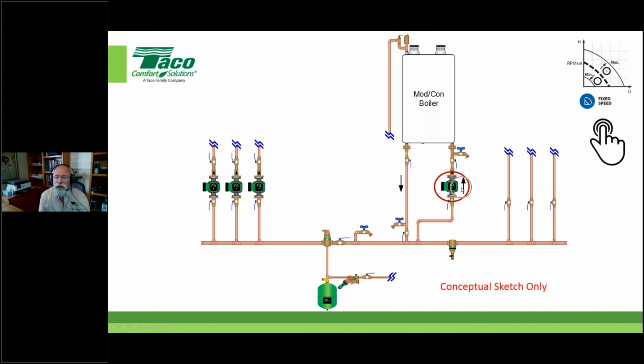So the reason—notice no more control wire—it's very important now to get this circulator sized correctly, and we will talk about that. We'll give you some hints and things that in some cases change the way you've been thinking about this. I know others have noted, yeah, I've been oversizing that pump. Well, that's what these seminars are supposed to do: get you to quit just doing the boilerplate stuff, start thinking about what you're doing and why, and be able to back it up. That's what TACO's trying to do here—make sure you have a better understanding of why you size the way you do.